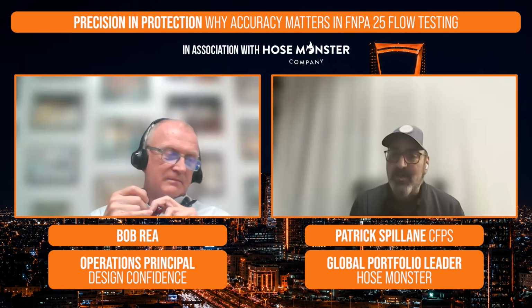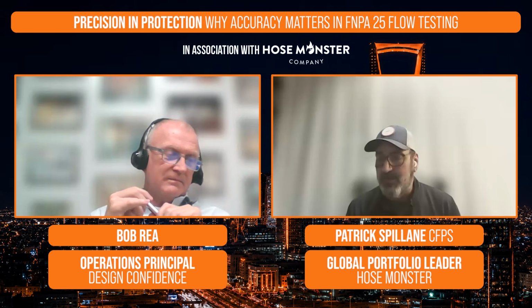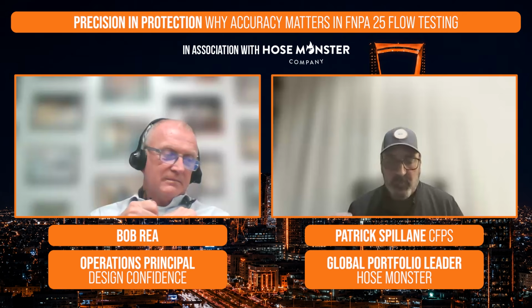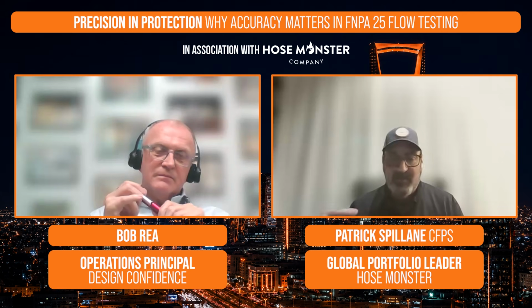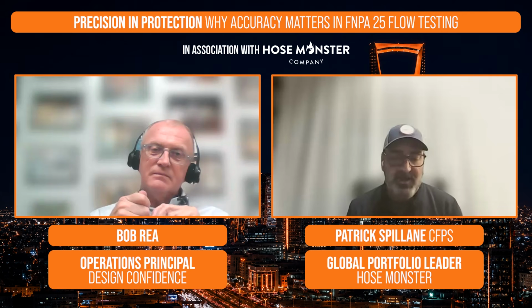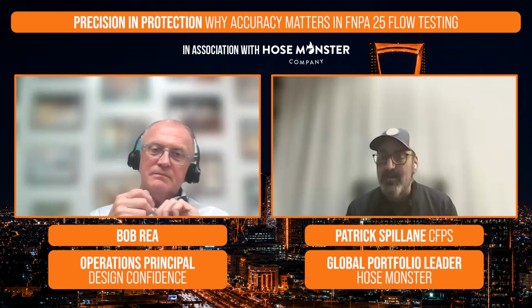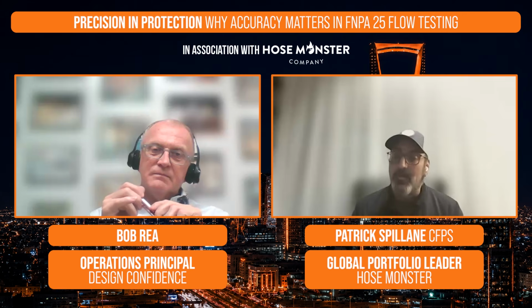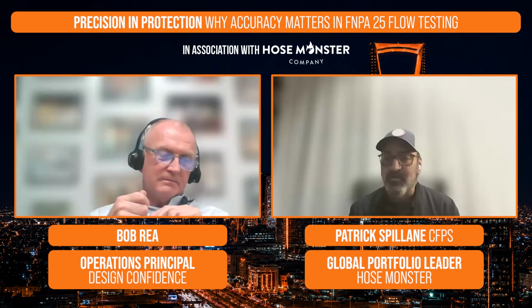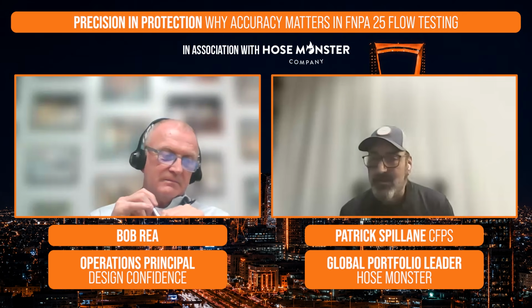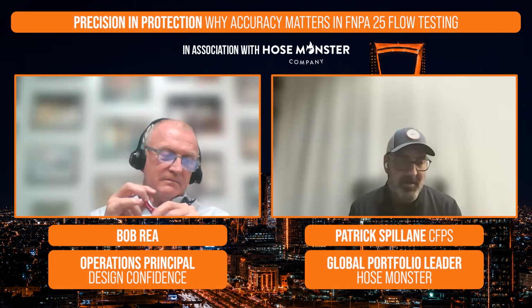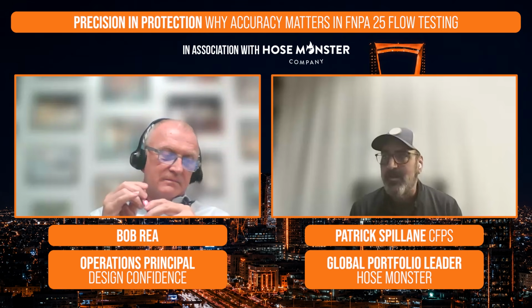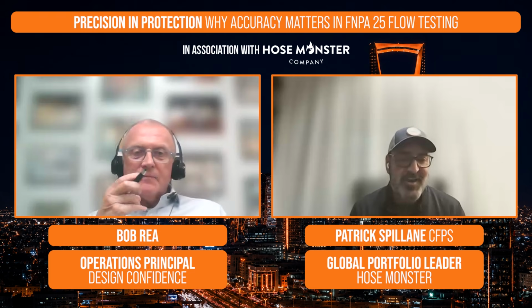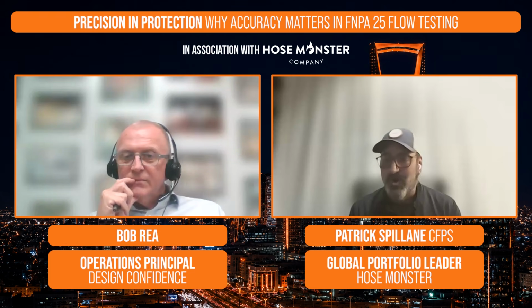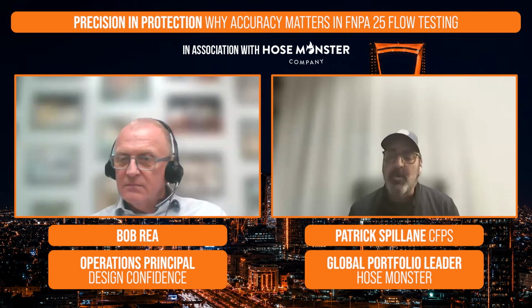We're going to be checking our packing glands. Both sides of the fire pump, we have our packing glands. The packing glands is what wraps around the shaft of that pump as that shaft is spinning to make sure it cools the shaft down. We want to make sure that those packing glands are dripping 1 drop per second on each side of the fire pump. Otherwise, we're going to see that fire pump overheat pretty quickly. If we see that fire pump start to steam up, most likely that's going to be a packing gland condition that needs to be addressed. We're going to be checking for any leaks that shouldn't be there. We want to make sure our relief valve is running properly. There's quite a few we can go through, right?